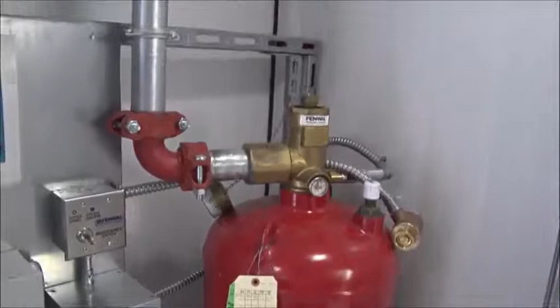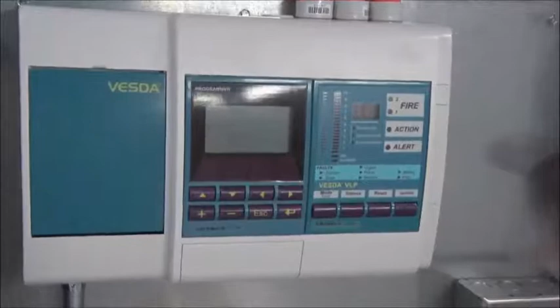This particular one has an FM200 fire suppression system. We typically default to a Novec 1230 - this is just an older demo, and at the time we chose FM200. But any fire suppression option is available. We'll have an optional VESDA early detection system, like the one Don's showing here. And then we're going to have some control panels. We can tie the control panel in with the EPO if we want. We can have different control setups and configurations depending on your particular needs.